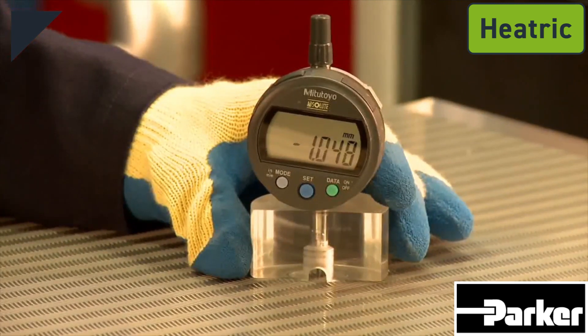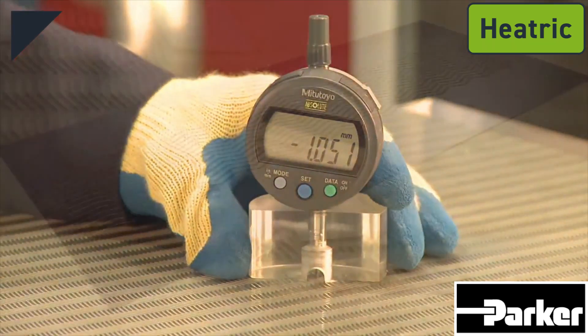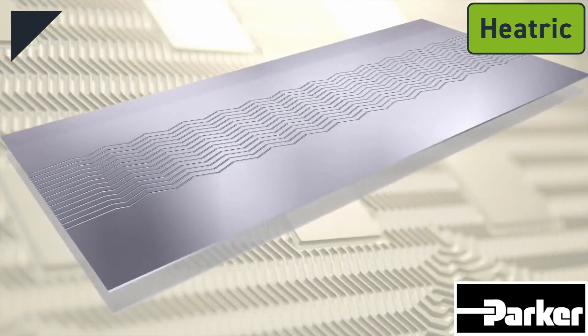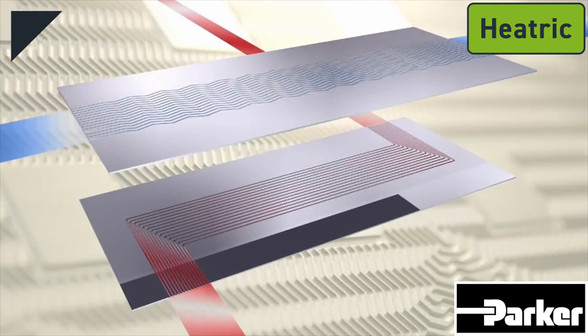These fluid flow channels are typically 2mm wide and 1mm deep semi-circles. The plate layout and flow patterns for the cold and hot sides of the exchanger are designed to suit the particular duty.